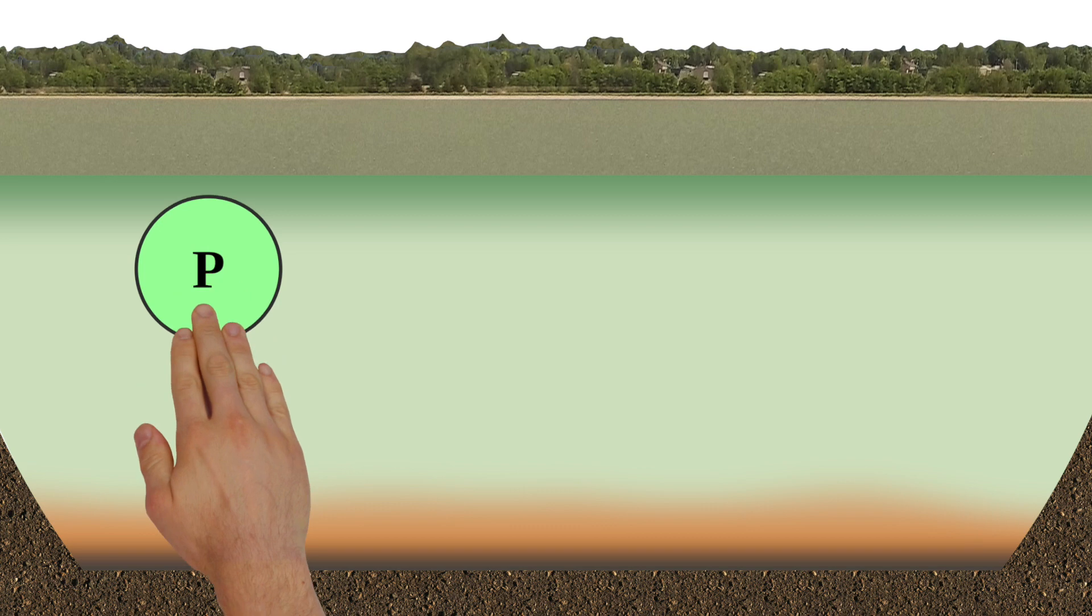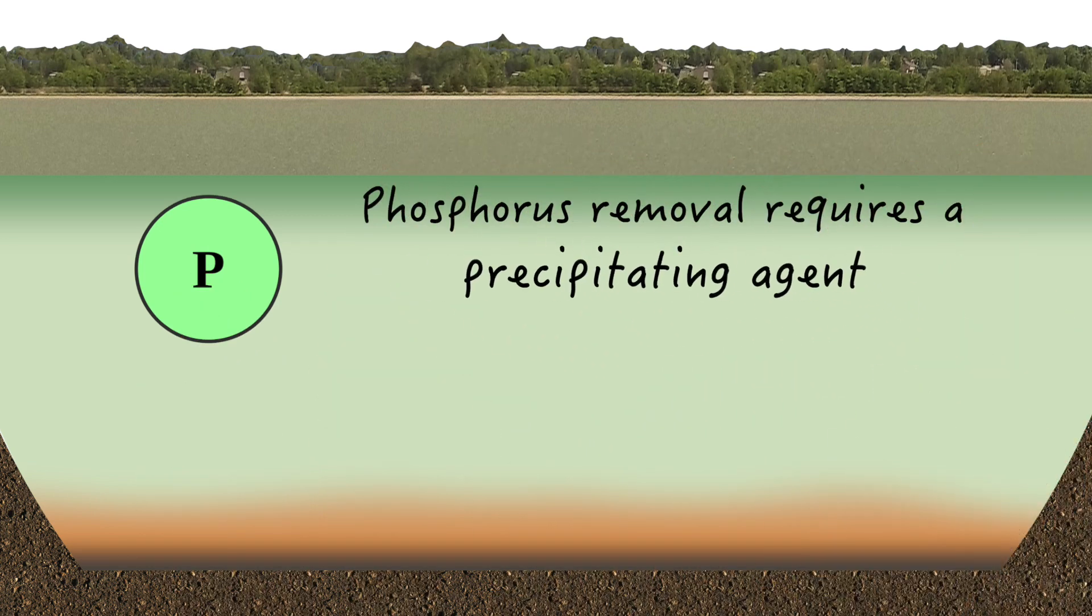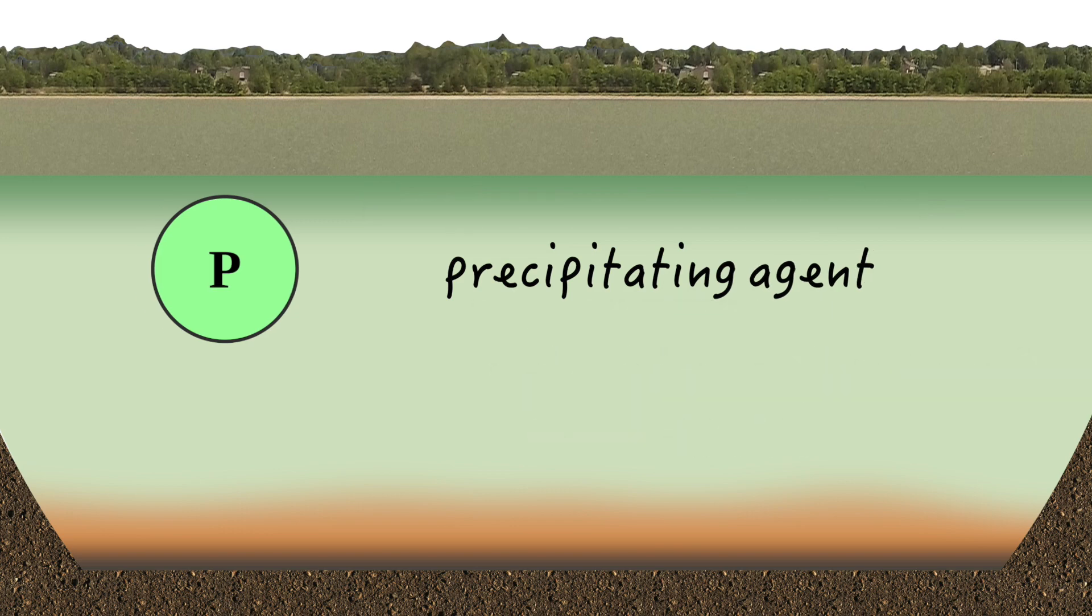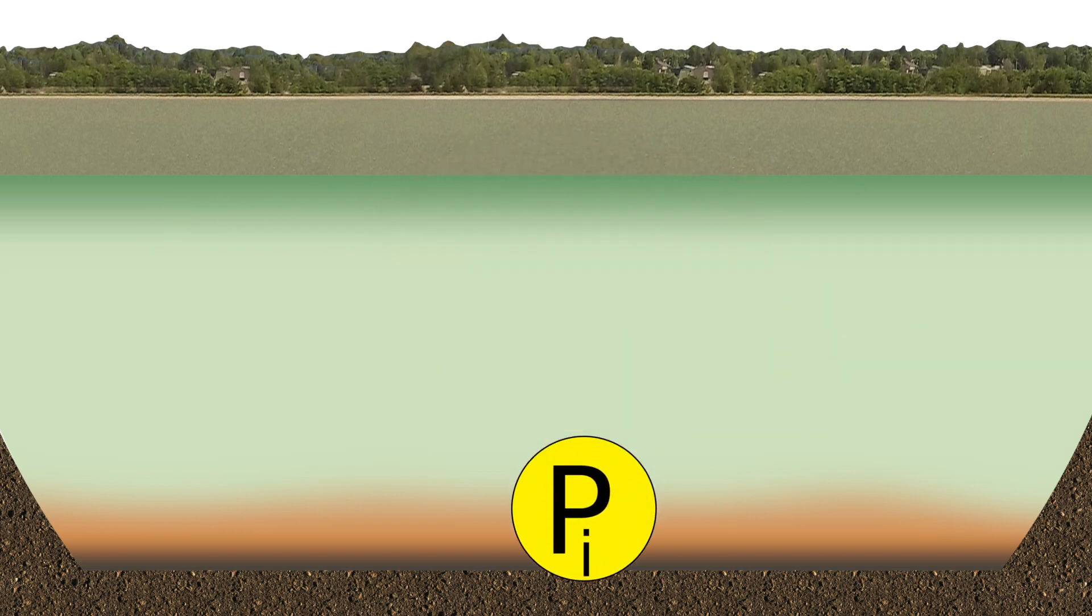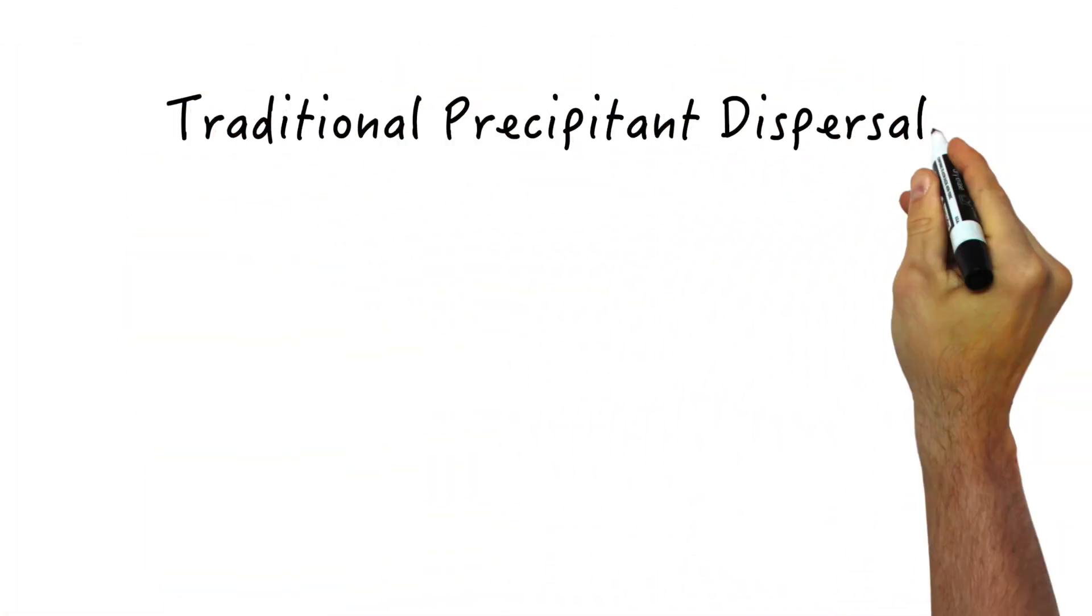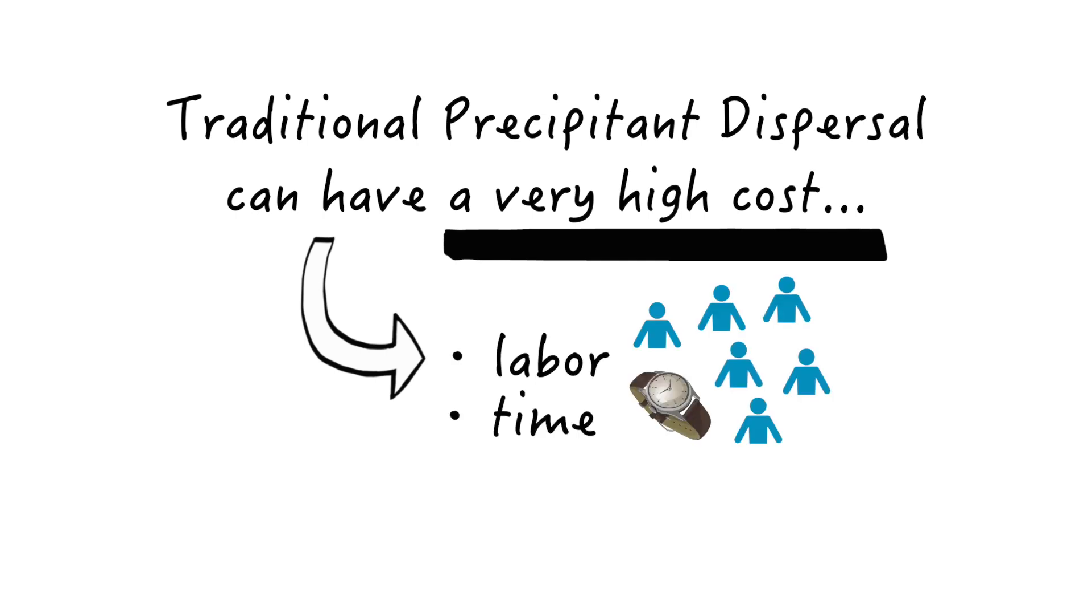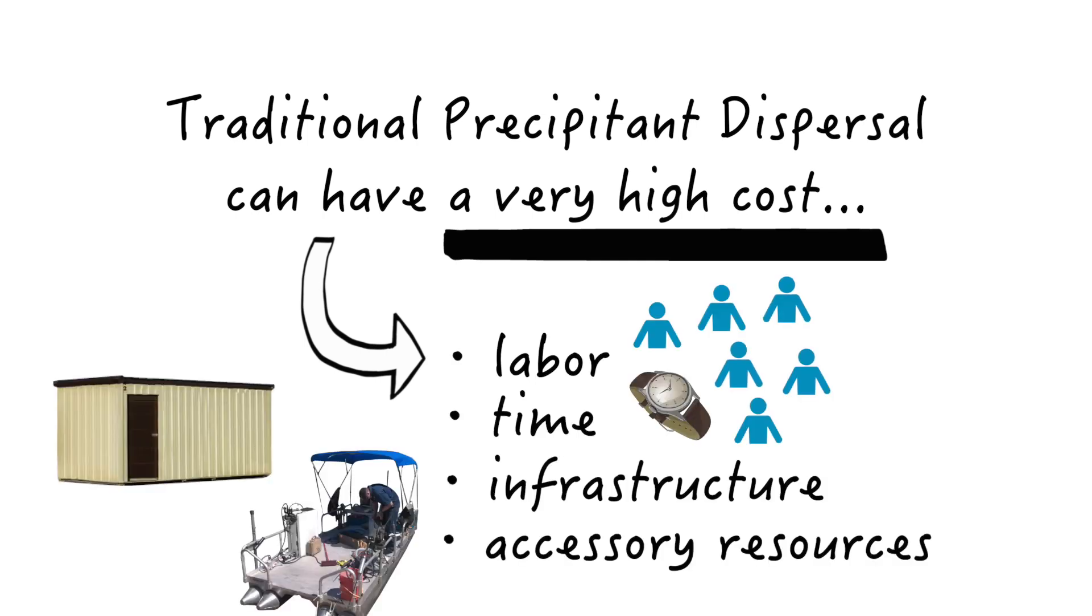So let's get our removal on. Phosphorus can be removed from a lagoon by applying a precipitating agent like aluminum sulfate or ferric chloride. Once precipitated, the phosphorus harmlessly falls out of the water column and into the sludge sediments. Precipitant dispersal is a very hands-on and costly process requiring extensive labor, time, infrastructure, and accessory resources.